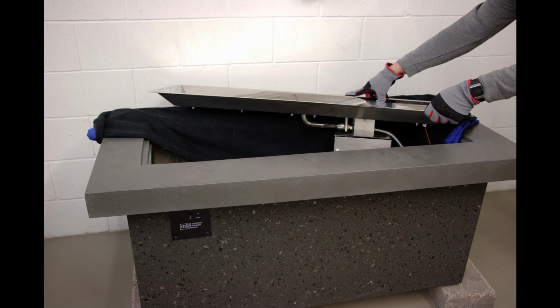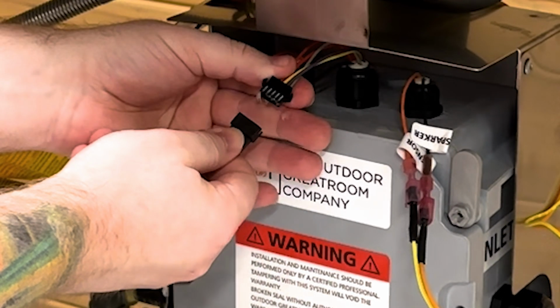Set the burner on top of the pit enclosure. We recommend laying down a heavy drop cloth or towel to protect the top of the fire pit from scratches. Connect the gas flex line to the inlet section of the valve using 2 adjustable wrenches. Check all other connections for tightness before proceeding. Now, let's connect all your wires.